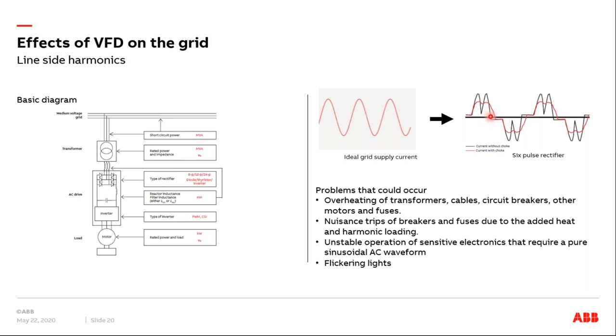So you would add basically a lot of additional peaks of current to your system. If, for example, your transformer, your switches, and circuit breakers, you would add a lot of additional load to this because of these harmonics. So basically what could happen, because of these added peaks of harmonics, you could overheat your transformer cables, circuit breakers, even other motors that are on the same line. You could have nuisance trips because of added heating. And if you have other sensitive electronics around that operation, then you might trip them. And also you could have issues with your lights because of this kind of harmonics.